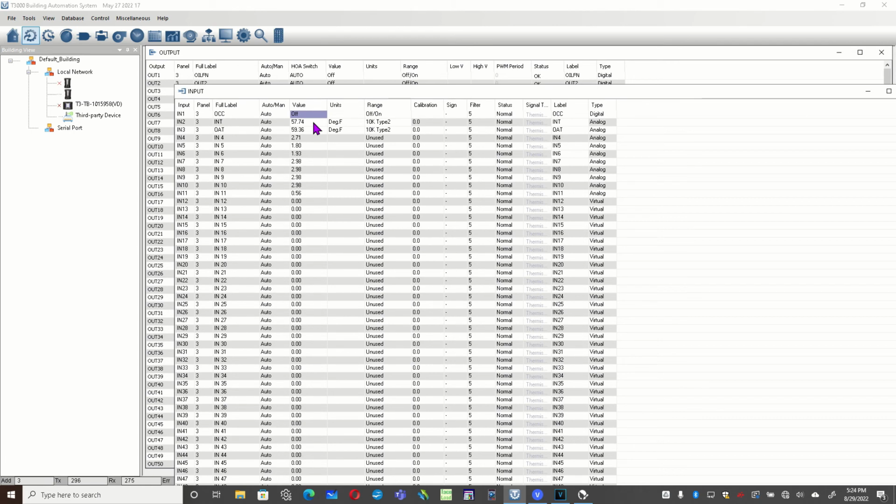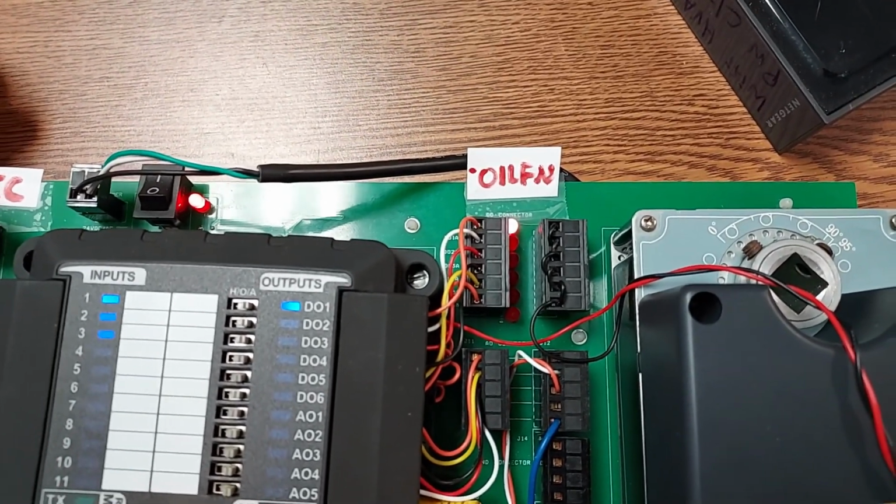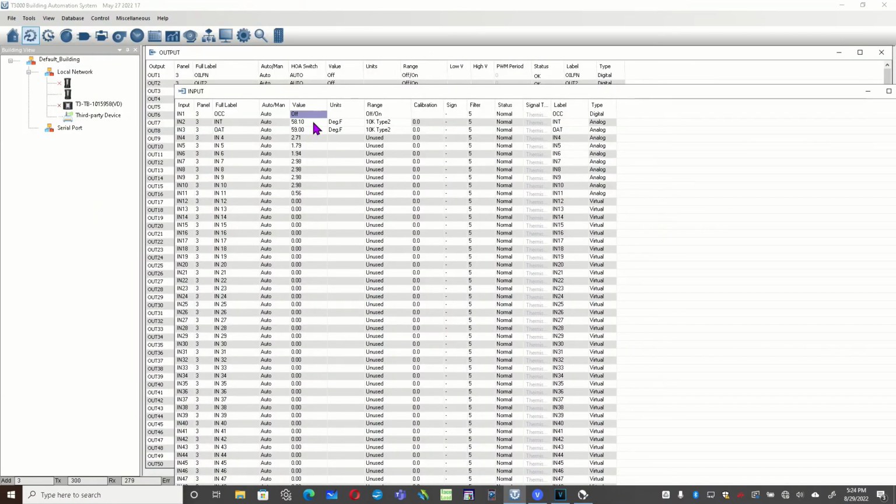We're going to press the occupied button for a second here, and the oil furnace starts, and it's going to run 15 minutes and warm up whoever's in there. They can be as comfortable as they like. They just have to keep pushing the button. But because there's a 15-minute timeout, they can't possibly leave the thermostat set way up and waste fuel. All right, that's it. We wrote a basic program, and it works.